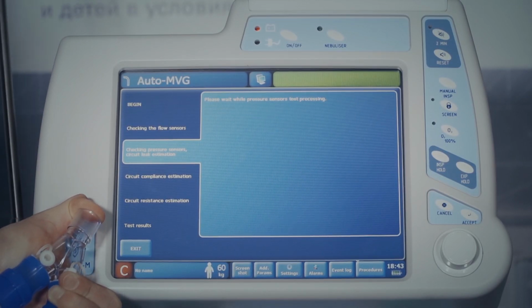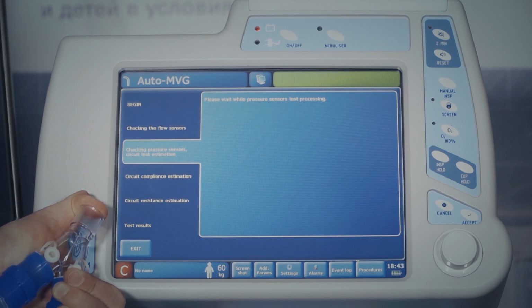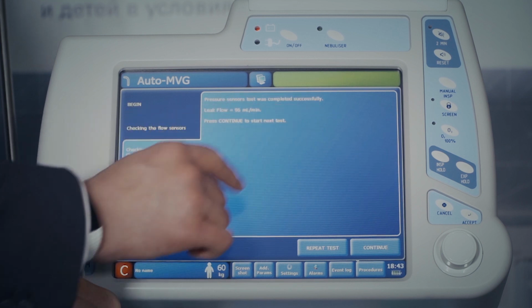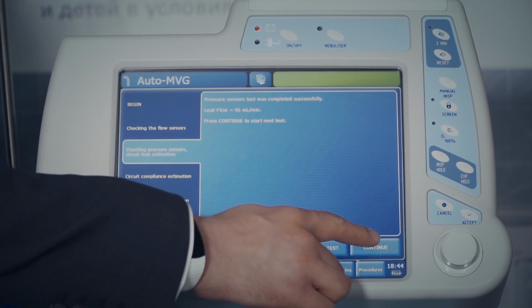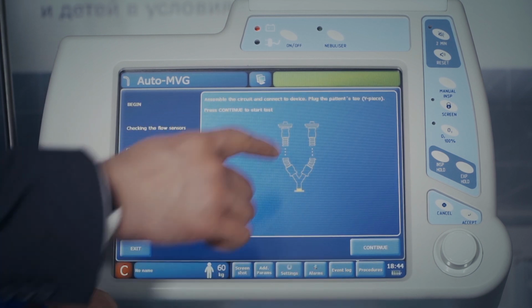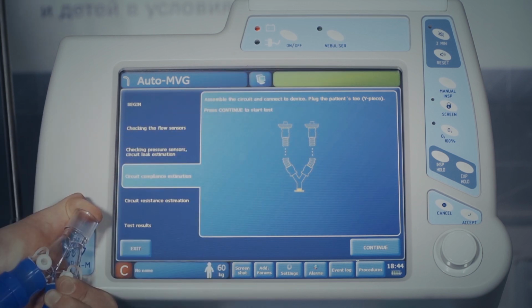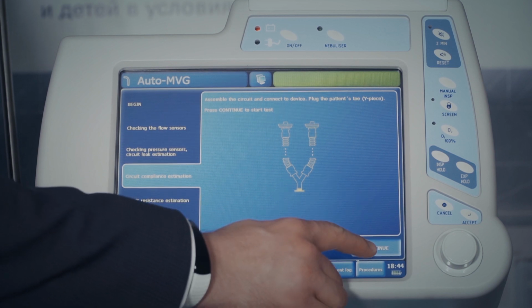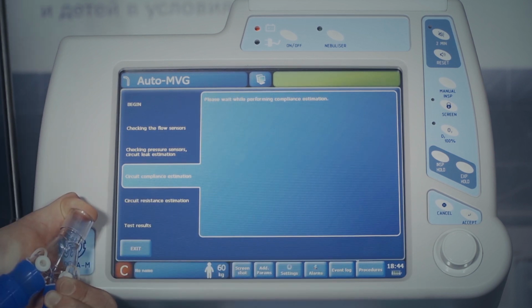Close the Y from the patient's side. This can be done with the use of a plug or with hand while wearing sterile gloves. Press Continue. If the test has been completed successfully, press button Continue to proceed to the breathing circuit compliance test. It is a very short test, which shall also be performed with Y closed from the patient's side.